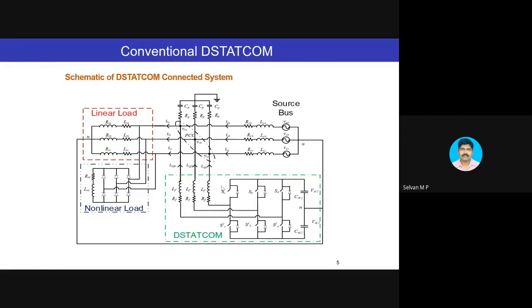Of course, the active part is not my botheration. Only the reactive part is my botheration. How much reactive current is required by the load should be provided by the compensator. That is the idea. So this is a STATCOM connected system. You can see that this is a source or a grid, whatever it is. You can say this is the transmission line, which is feeding a linear load, an RL load, and I have a non-linear load which draws a harmonic component of the current. And the point at which the load is connected is called the point of common coupling, where I want to connect a STATCOM. Since it is used in a small distribution system, it is called a D-STATCOM.